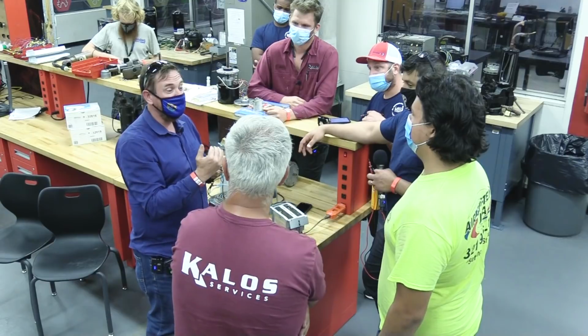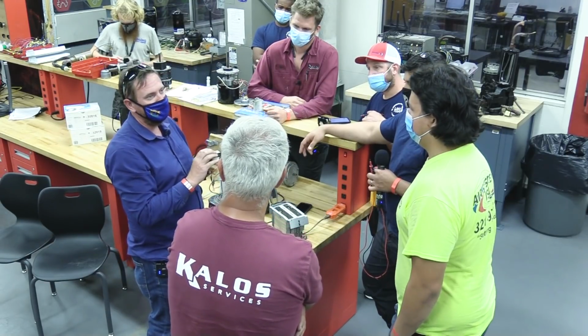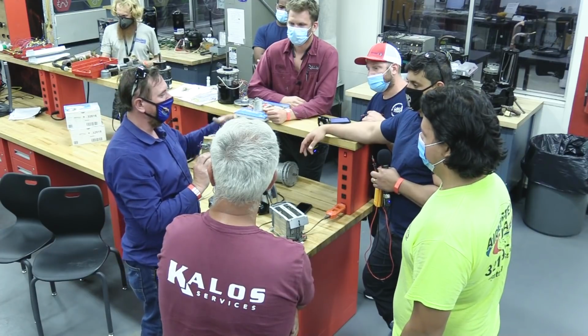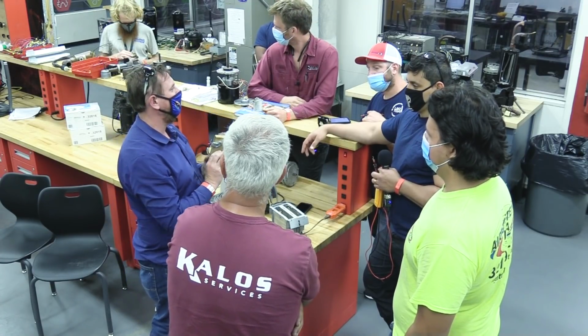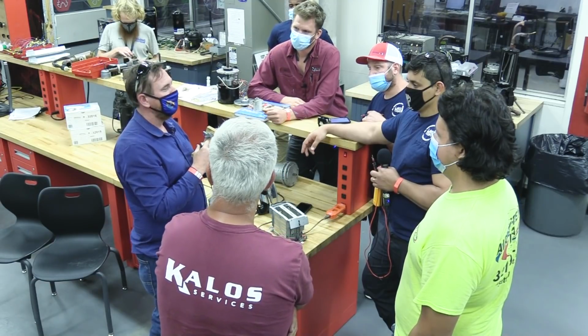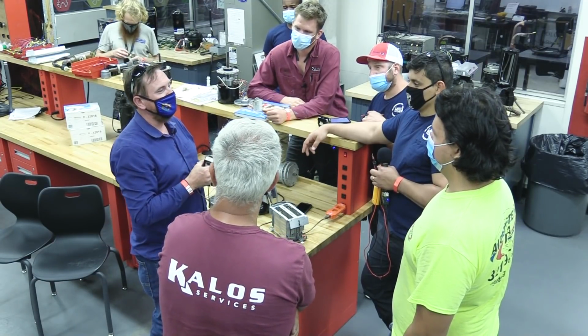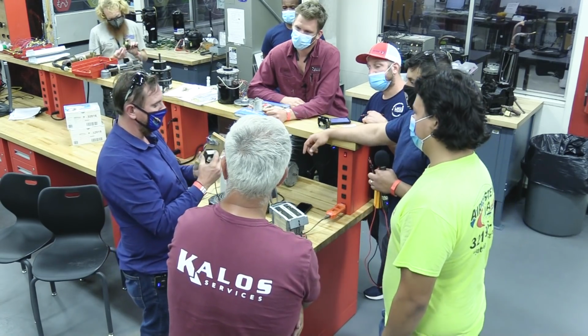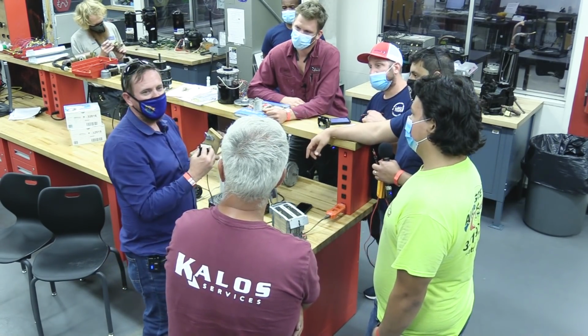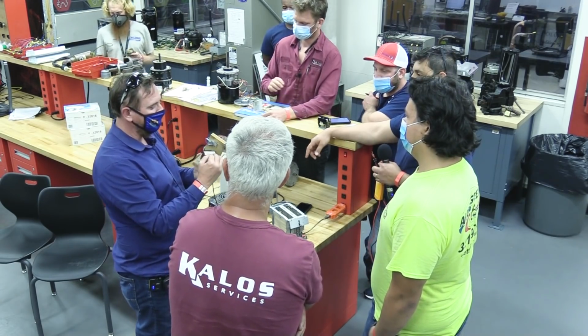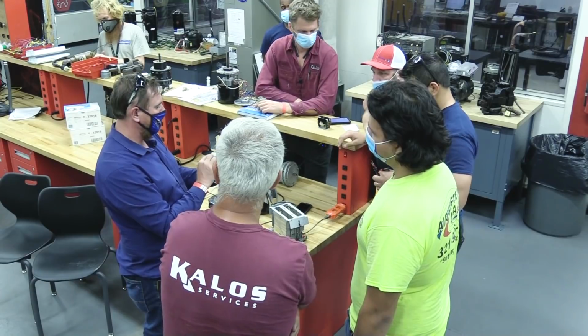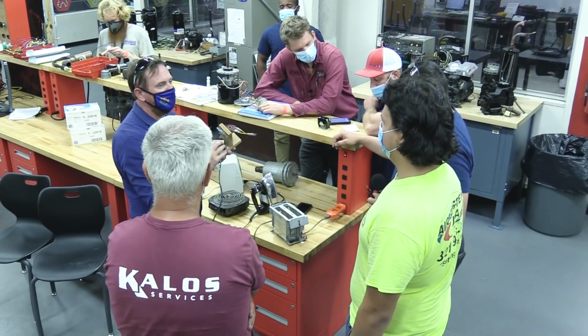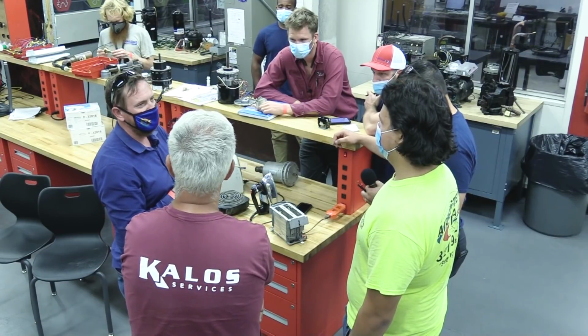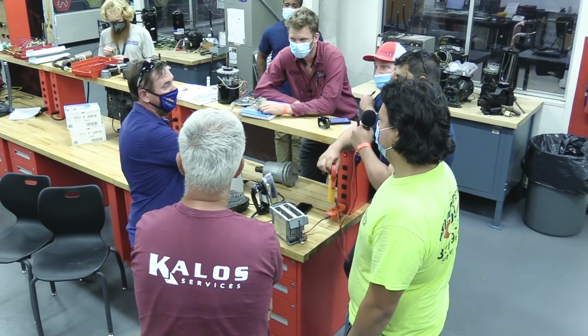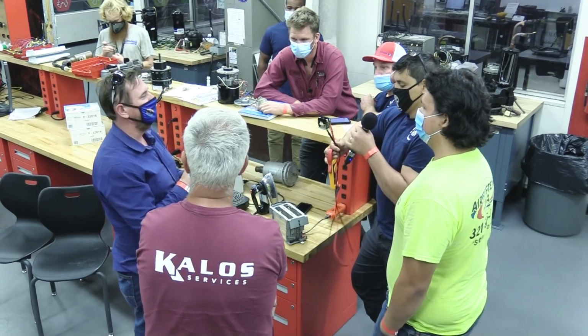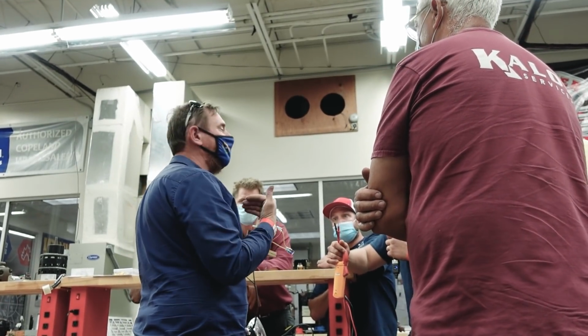And when you're changing out a transformer, it's important to know that number because if it's only rated for 45 watts, and all of your low voltage loads you need 75 watts, is it going to be built strong enough? No, you're going to have problems. Sometimes you may add some low voltage circuits to the unit. You got to make sure your transformer can handle the watts or the VA of that unit. So VA, volt amp, so this one's worn off. I've had it for so long, you can't see it anymore. But it's a very low volt amp rating. In my truck, I only kept, I think it was 75 VA transformers because a 75 VA transformer will handle 75 VA loads and also 45 VA loads. Just because it will handle 75 watts doesn't mean I have to flow 75 watts through it.